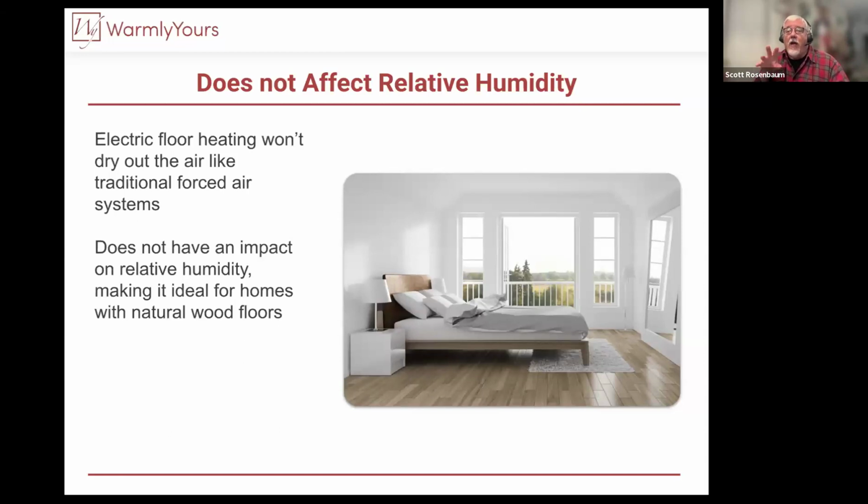And that's what's drying the system up. So when you're installing a floor that has a humidity requirement, like if you buy hardwood or that sort of stuff, and they say it must be in a relative humidity band between 30 and 60%, you're going to be responsible for keeping that product within 30 to 60%. That's up to you, either using humidification in the wintertime or dehumidification in the summertime.